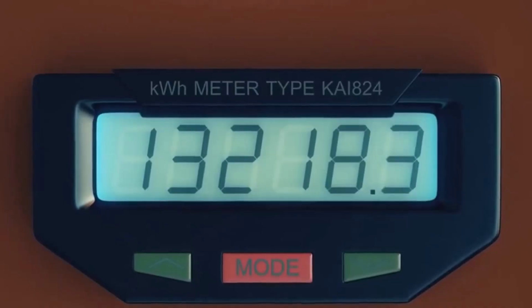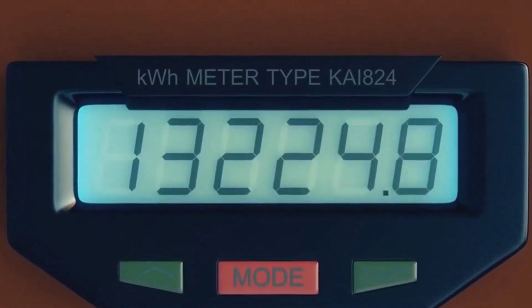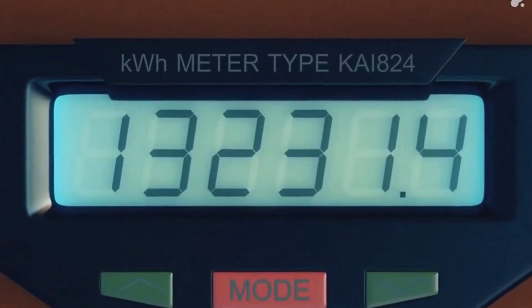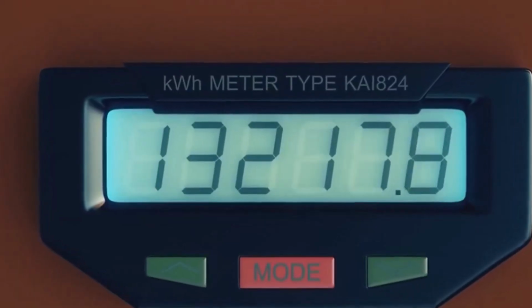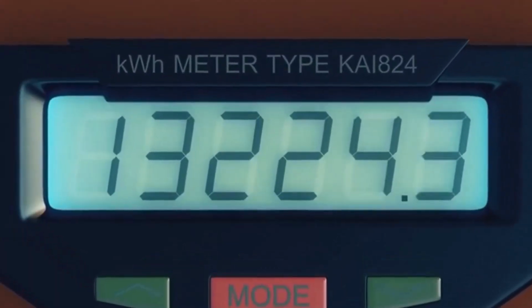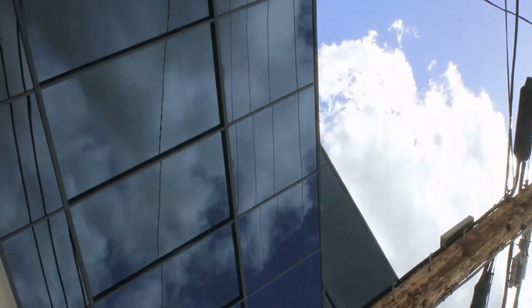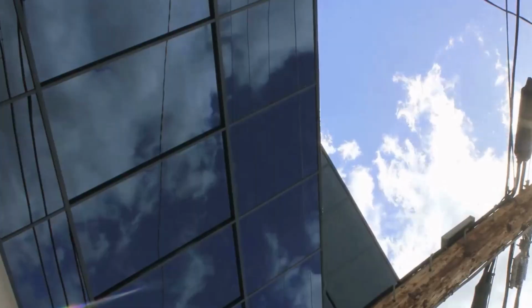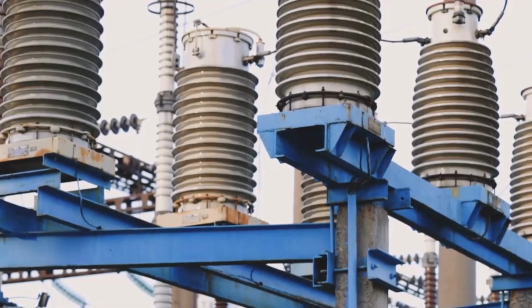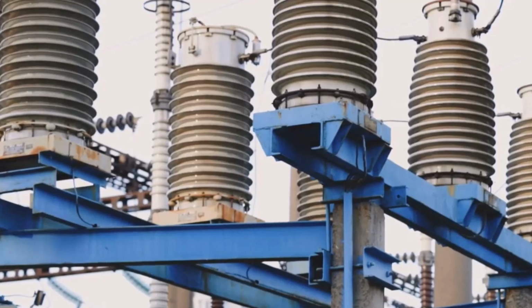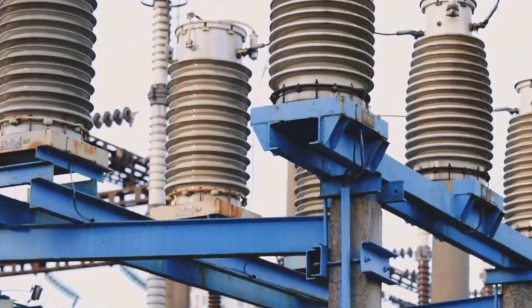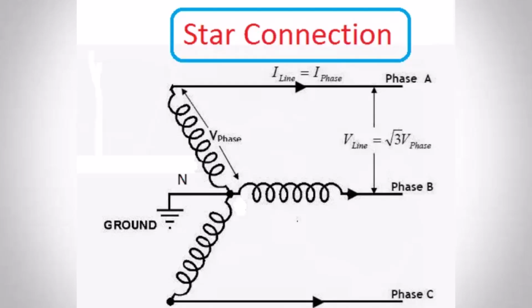For example, if the phase voltage in a system is 277 volts, the line voltage would be 277 multiplied by 1.732, which equals approximately 480 volts. This is a very common voltage combination used in commercial buildings in the United States. This mathematical link is super handy for engineers because it allows them to design systems with multiple voltage options available from a single source. It's a simple rule. Line voltage equals phase voltage times the square root of 3. This predictable relationship makes calculations and system design much more straightforward and reliable for everyone involved.